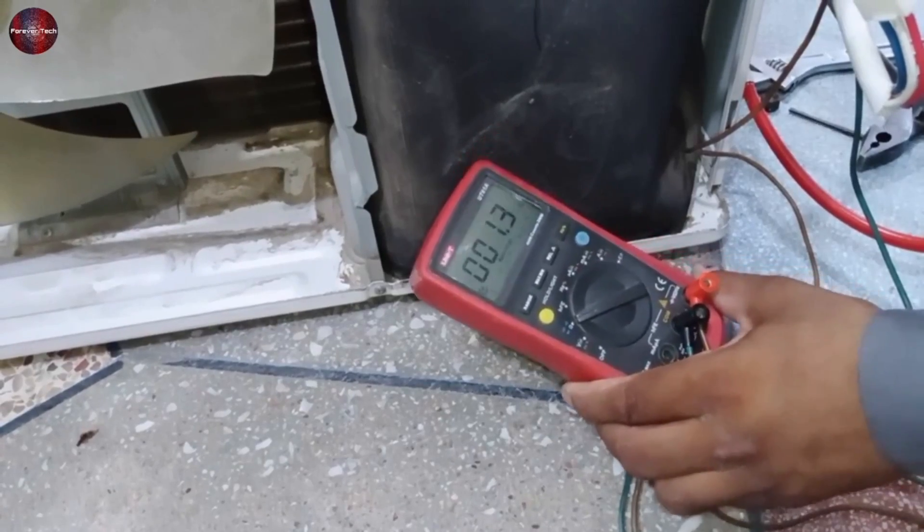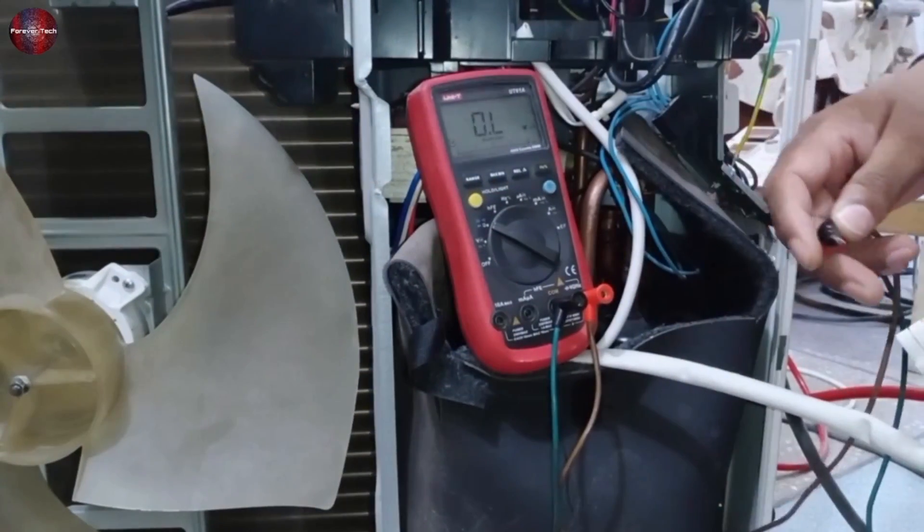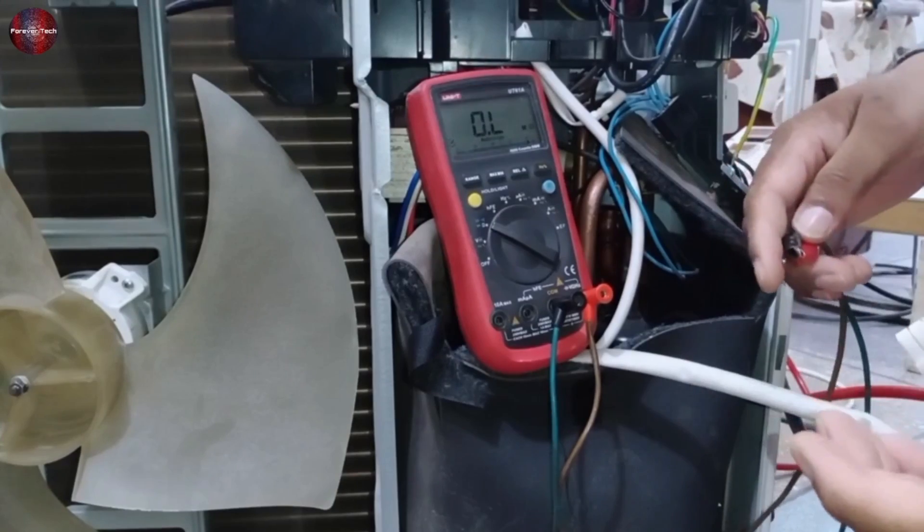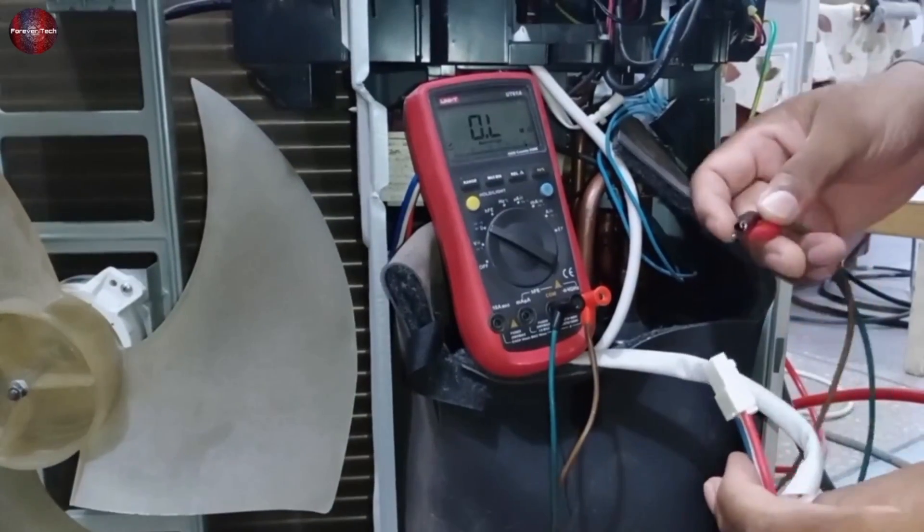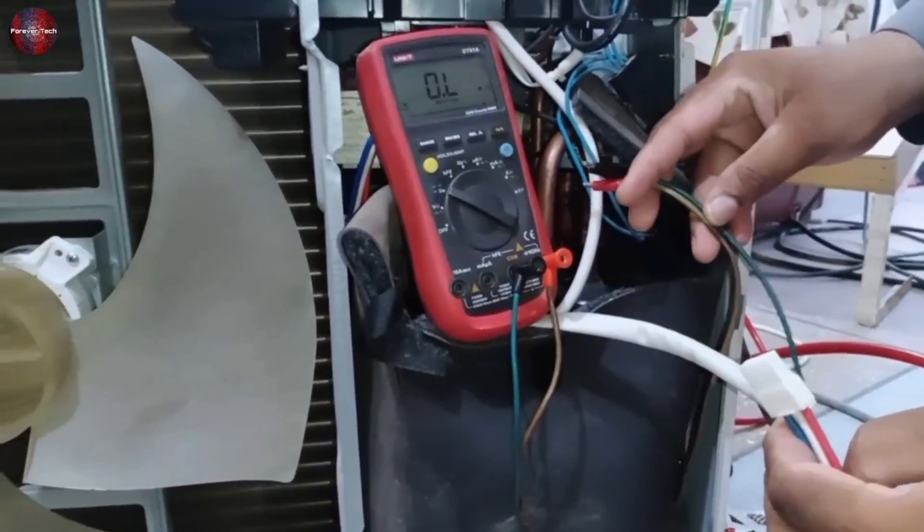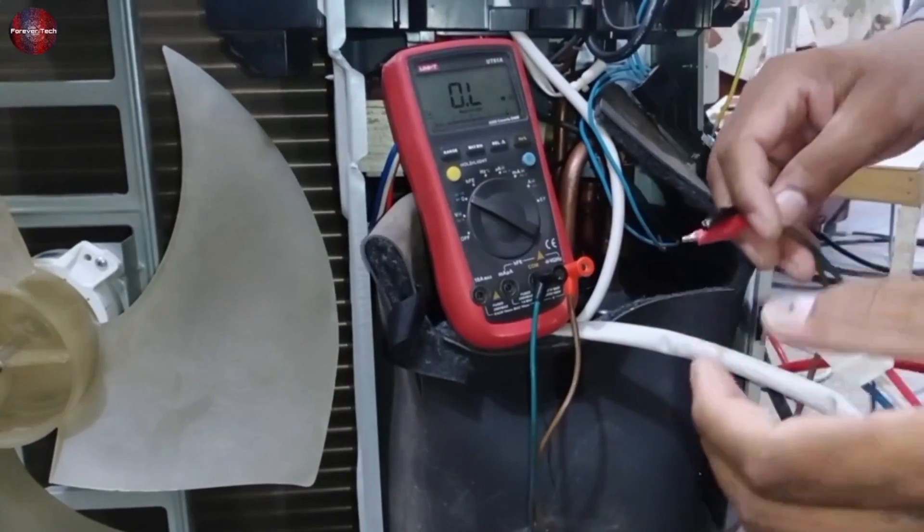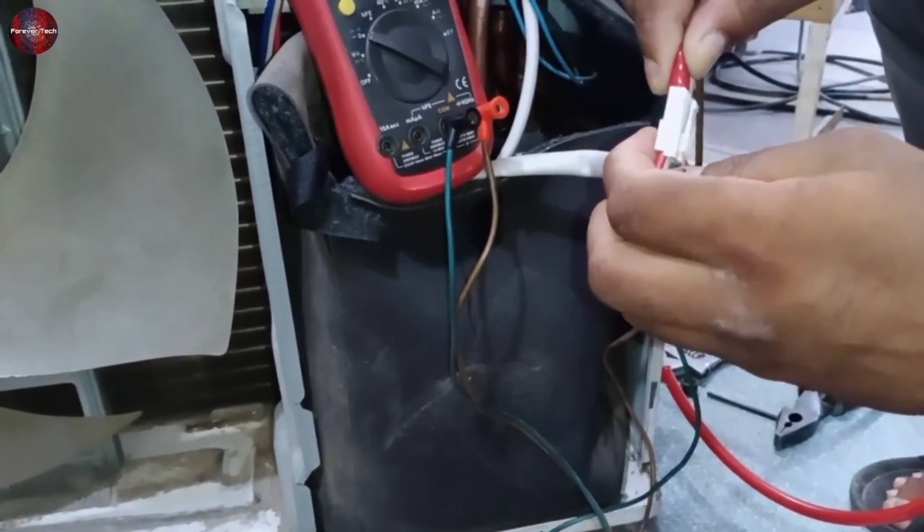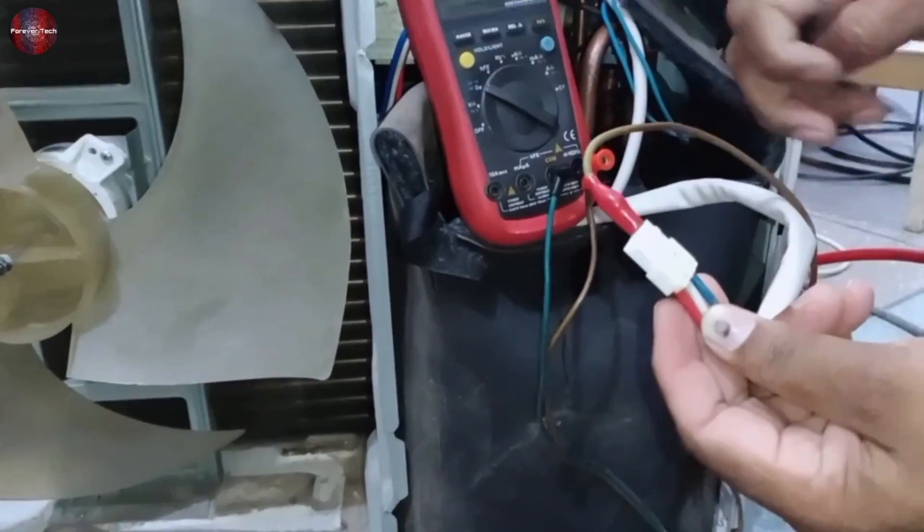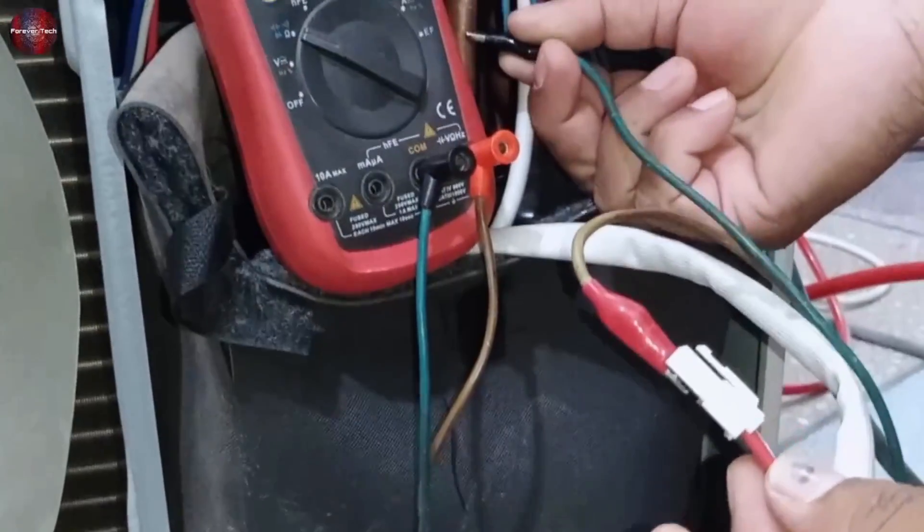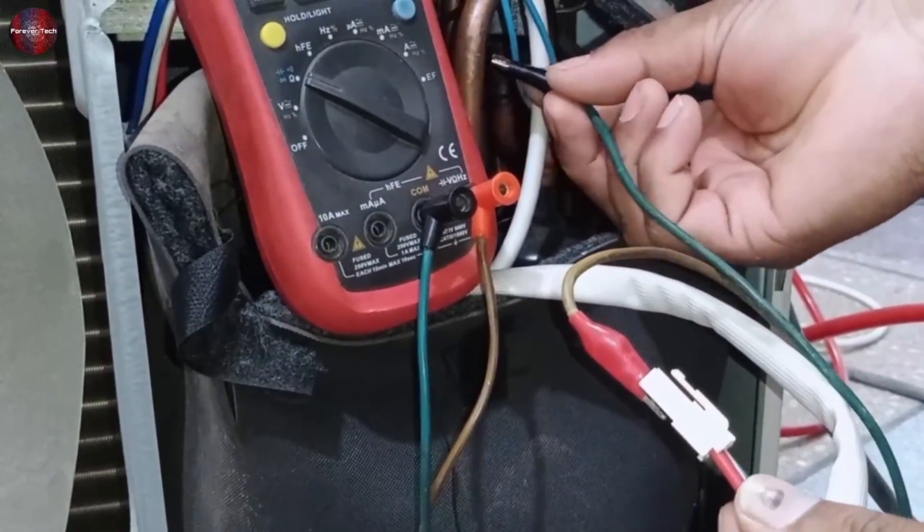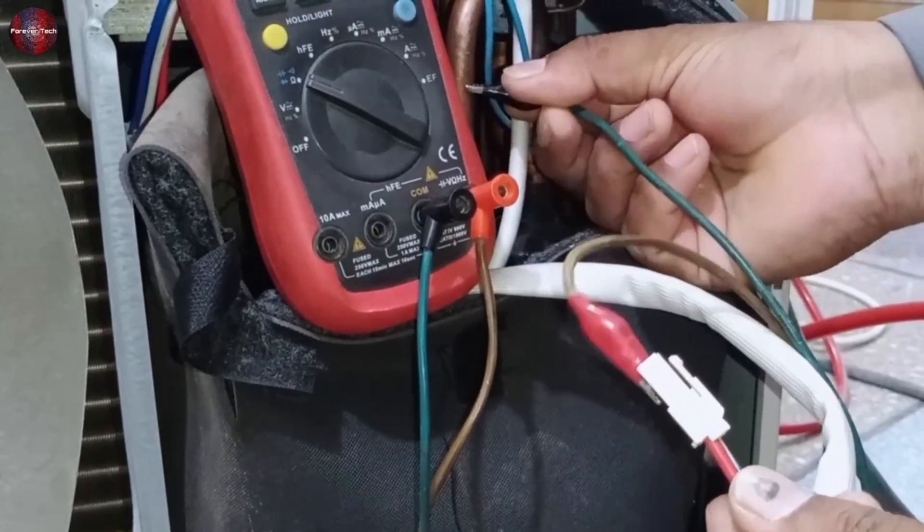Now let me tell you about the next test. The next test for the inverter compressor is significant. You have to check the compressor's leakage and whether the compressor's winding has any leakage present in it or not. You have to attach any probe of the multimeter with the compressor terminal connector and attach the second probe of the multimeter with the copper pipe, which should be welded with the compressor.